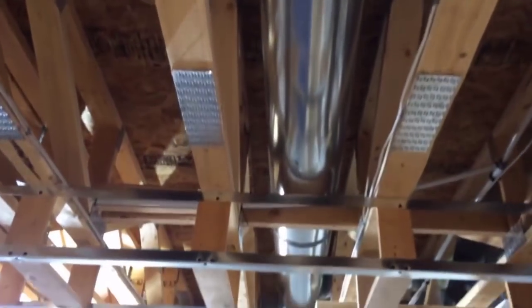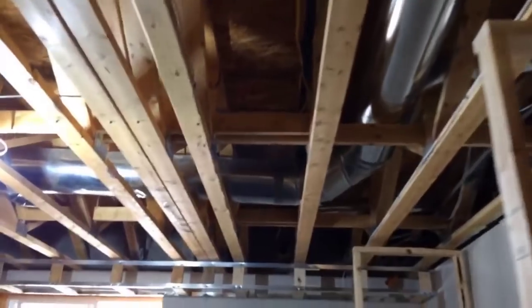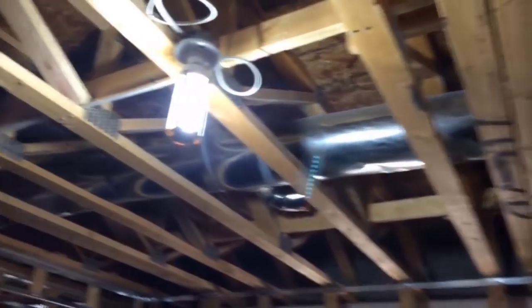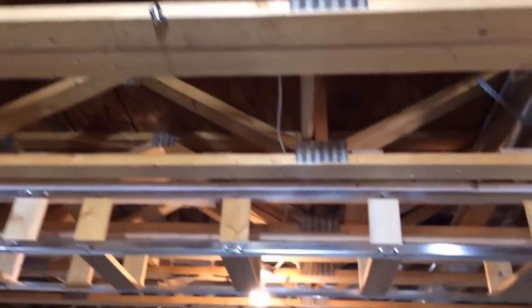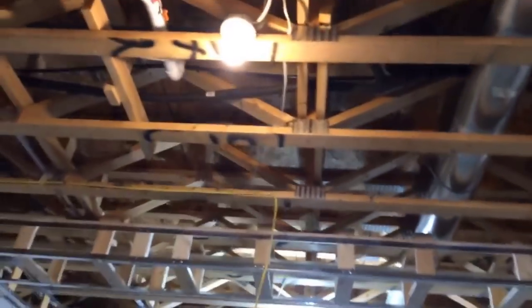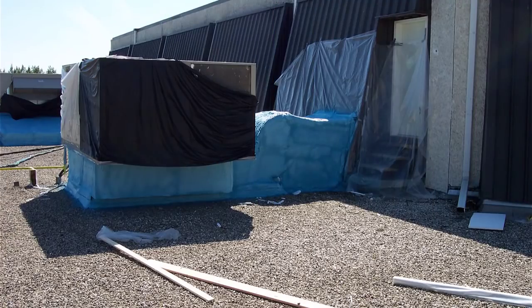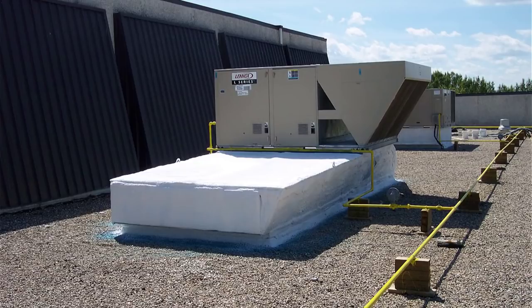So ductwork being sprayed is a good way to go. It seals everything up very nicely. It keeps the ducts from being rattly and tinny. Condensation can be eliminated if they're sprayed correctly. It keeps the ducts very warm, and keeps the floor very warm. And in commercial settings, it can be an exceptional way to treat rooftop units and what have you. Although if you're on the outside of the building, you're going to have to put some sort of protective coating over the foam to keep the ultraviolet light off of it.